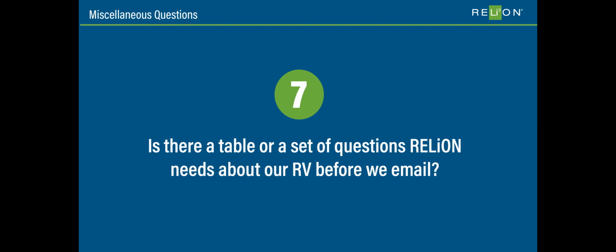Christine, who's answering the Q&A in the chat, that HP batteries can be hooked in parallel. However, we have concerns about the peak current, which should not be doubled. You can certainly add another RB300 HP to your system and connect it in parallel. You'll have increased continuous current. We wouldn't want you to double that, but I think that battery's rated at 100 amps continuous current, which translates to about 1,200 to 1,300 watts. Hooking a second HP in line with that, you wouldn't want to double your continuous to 200 amps or 2,600 watts, but you could increase it by about 75%. So that gives you roughly 2,000 watts or 150 amps. But the peak, the reason people buy the HP so they can go to 800 amps for 3 seconds, you don't want to double that. You want to keep that at a single battery rating.